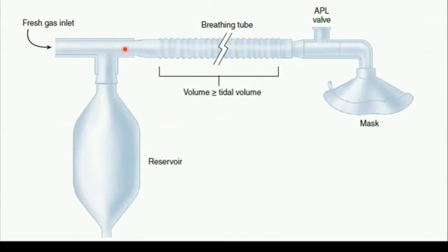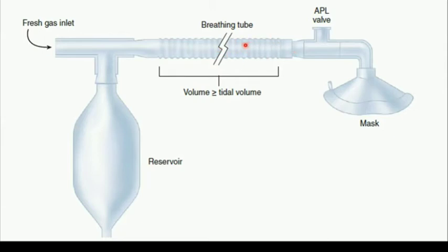Fresh gas enters through the inlet and the patient takes up the anesthetic gases. The patient exhales CO2 back into the breathing system, but fresh gas is continuously coming in, so pressure builds up inside the breathing circuit. The APL valve allows this pressure to be relieved.